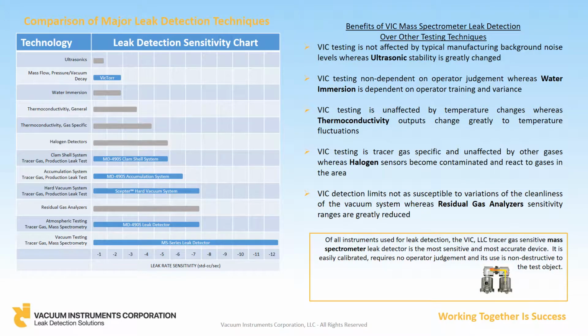So now that we have an understanding of the units of measurement, let's take the next step to determine the type of technology that could be employed. The chart here shows the various technologies as they relate to relative sensitivity or leak rate. As you move down through the technology column, you will note that the mass spectrometer vacuum testing method provides the broadest range of leak detection, from 1 cc per second to 10 to the minus 12 cc's per second, which, by the way, is 11 zeros followed by a 1.